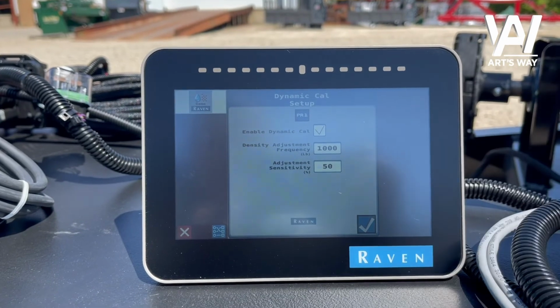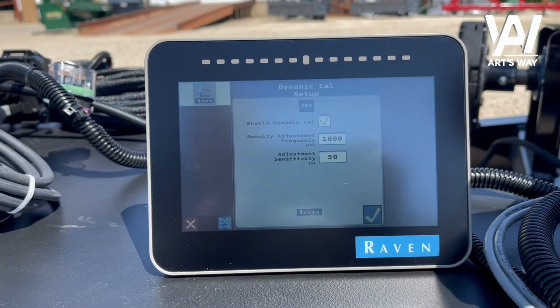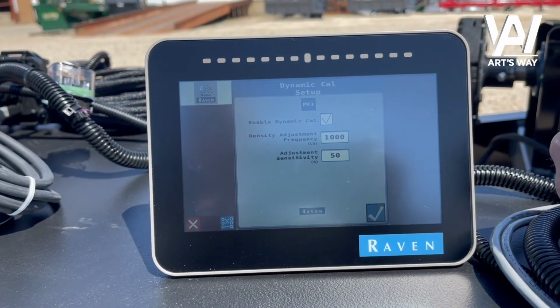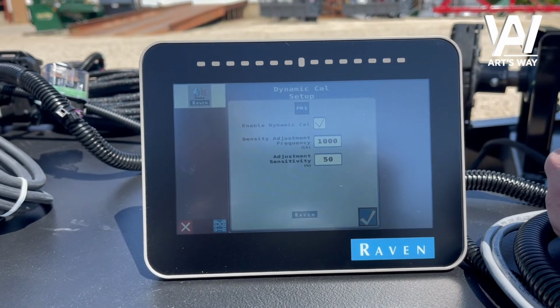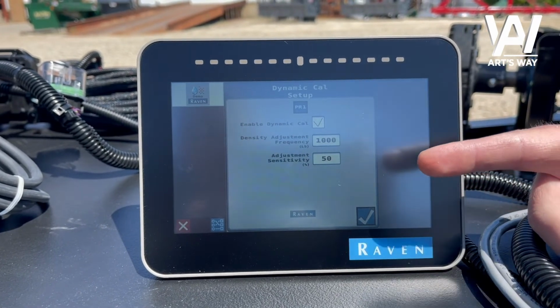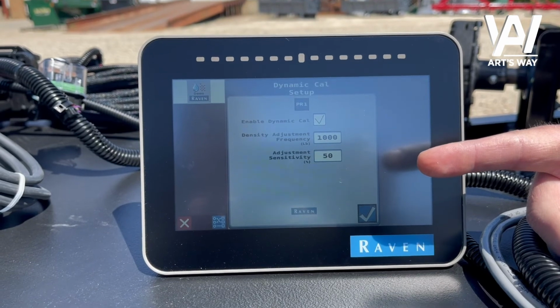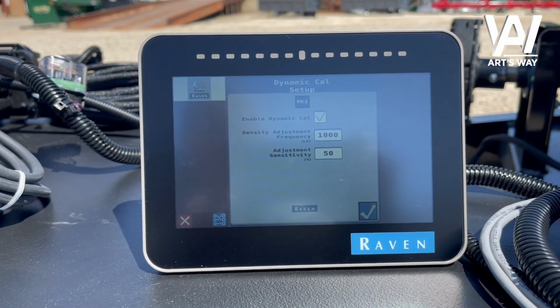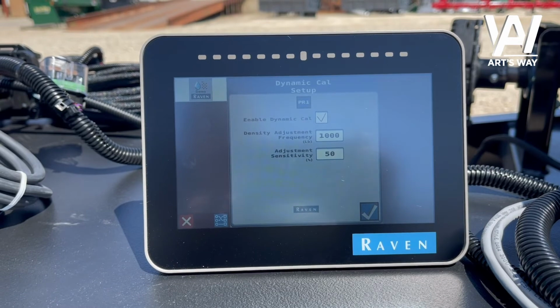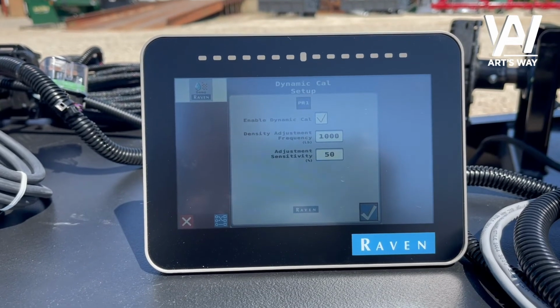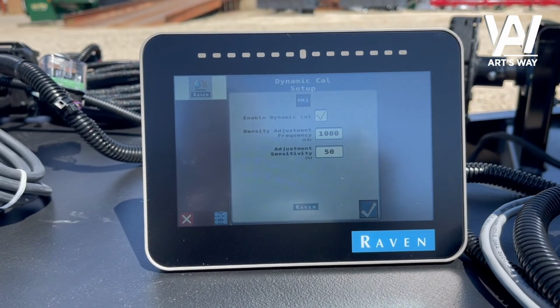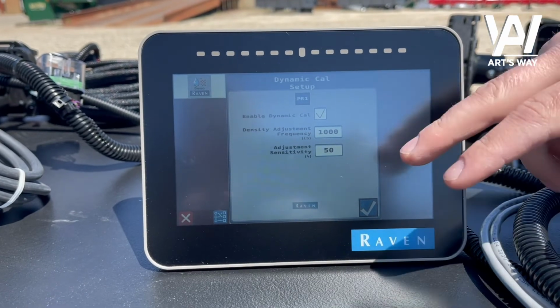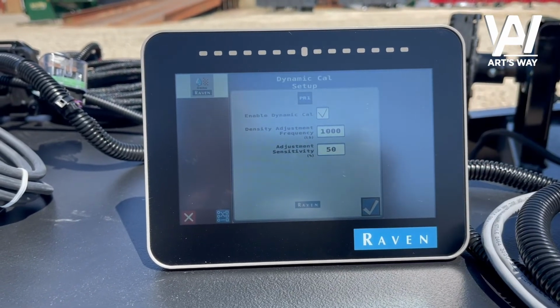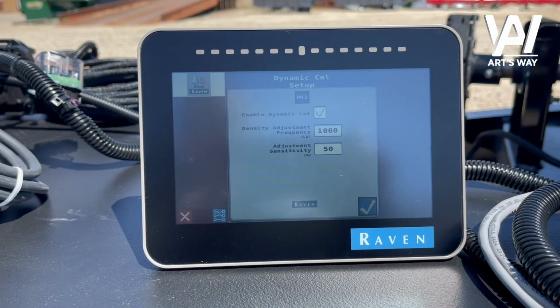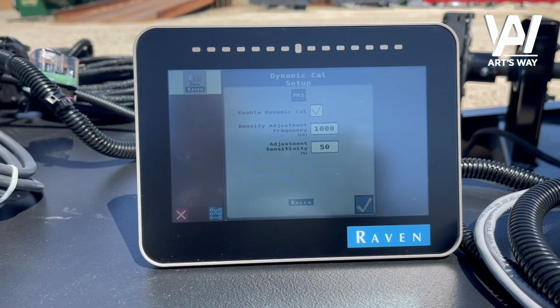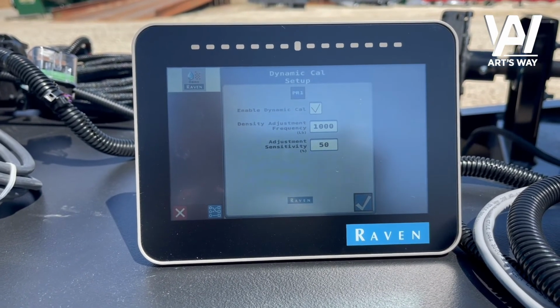The sensitivity value down there: if it's a really large swing that the system determines it needs to adjust, with a sensitivity setting of 50, we'll only make half of the adjustment in that one time that the system thinks it needs to change. You can adjust those values up and down a little bit. I just recommend not getting too far away from 50, because if there are large swings, you can see some erratic rate behavior.